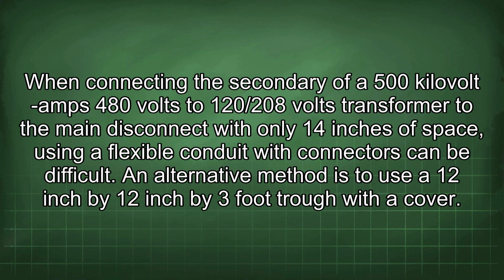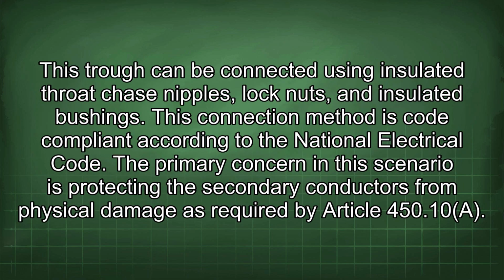When connecting the secondary of a 500 kVA 480 volts to 120/208 volts transformer to the main disconnect with only 14 inches of space, using a flexible conduit with connectors can be difficult. An alternative method is to use a 12-inch by 12-inch by 3-foot trough with a cover. This trough can be connected using insulated throat chase nipples, lock nuts, and insulated bushings. This connection method is code compliant according to the National Electrical Code.